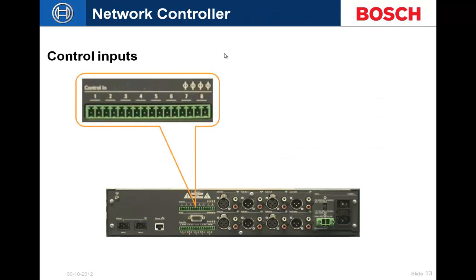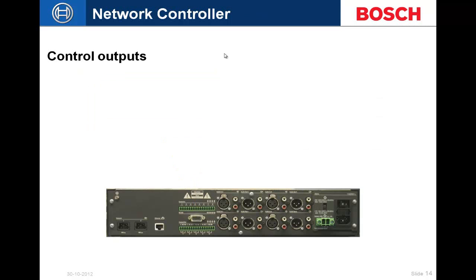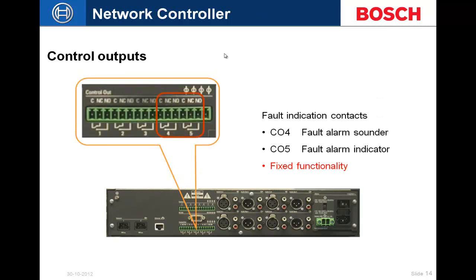On the back panel we have eight supervised control inputs. We do not recommend a common ground if you're running multiple contact closures to a location — use individual pairs of wires for each contact. Control outputs four and five are dedicated to fault alarm sounder and fault alarm indicator respectively. Those are fixed functionality and cannot be changed; they are dedicated to fault statuses.